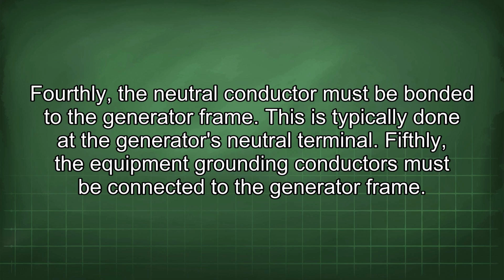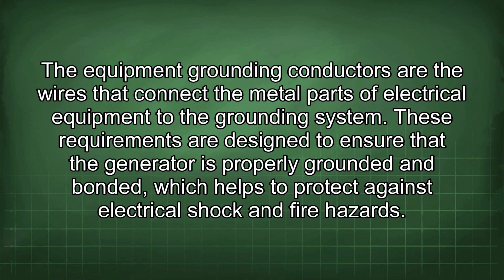Fourthly, the neutral conductor must be bonded to the generator frame. This is typically done at the generator's neutral terminal. Fifthly, the equipment grounding conductors must be connected to the generator frame. The equipment grounding conductors are the wires that connect the metal parts of electrical equipment to the grounding system. These requirements are designed to ensure that the generator is properly grounded and bonded, which helps to protect against electrical shock and fire hazards.